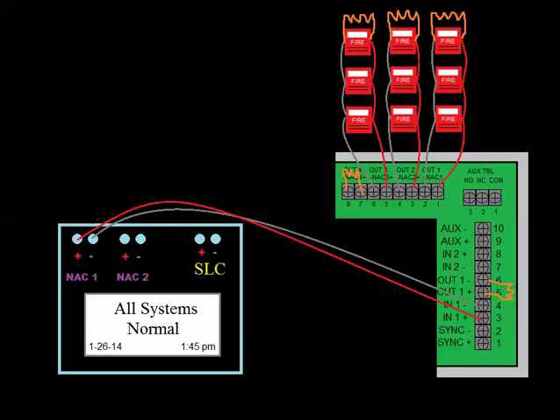And what would determine that is how you're triggering it. If your fire alarm panel had that capability, most new addressable fire alarm panels have the synchronization capability built into them. So I would go into programming and tell this panel, NAC1 is, let's say, a System Sensor sync. That's the type code of that NAC. Well, now that's going to have that sync code on there.